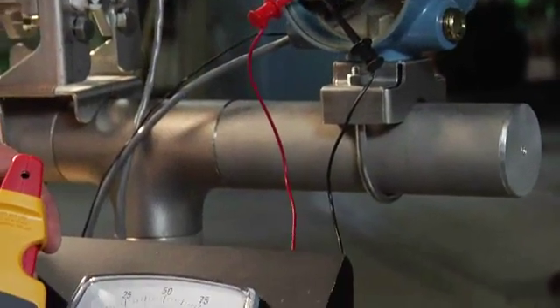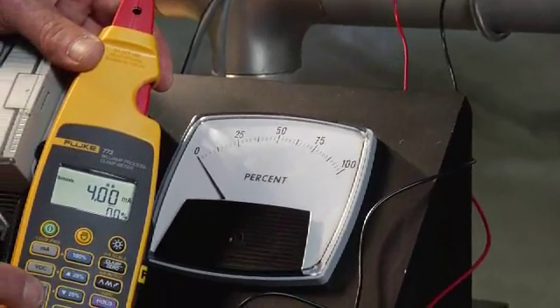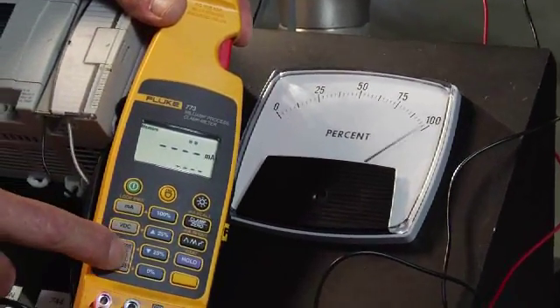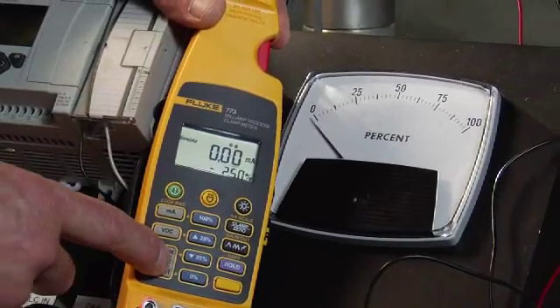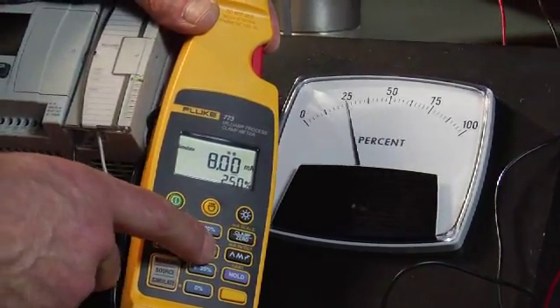If the local indicator responds correctly to the milliamp simulate signal, you have identified that the power supply and the loop are operating correctly and that the source of the problem is likely the transmitter or the input to the transmitter.